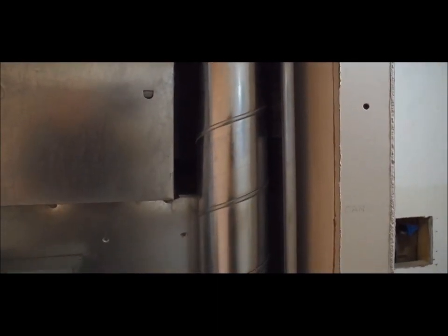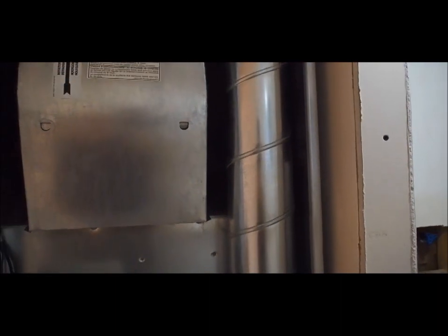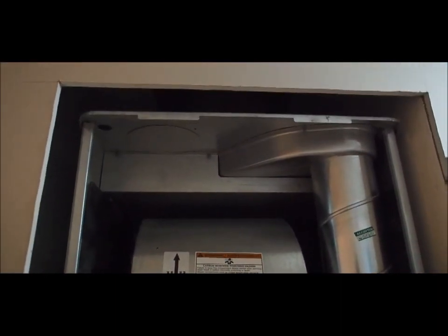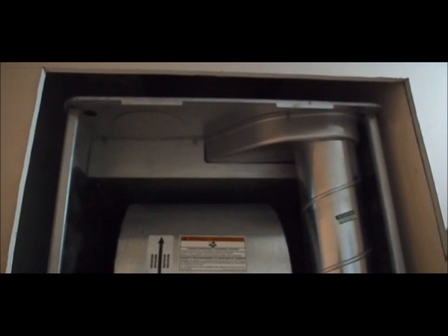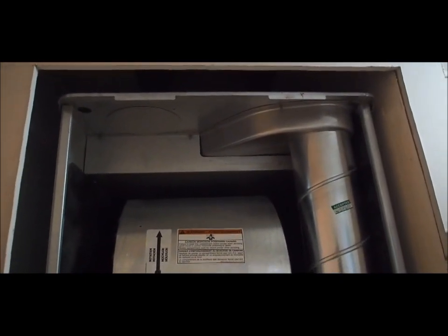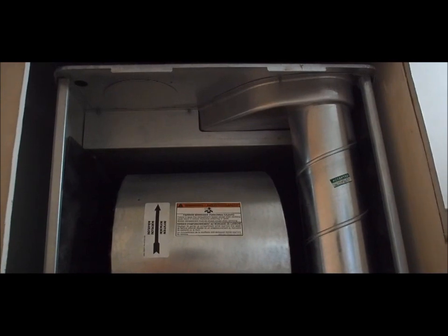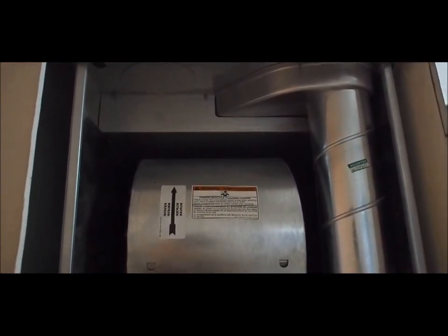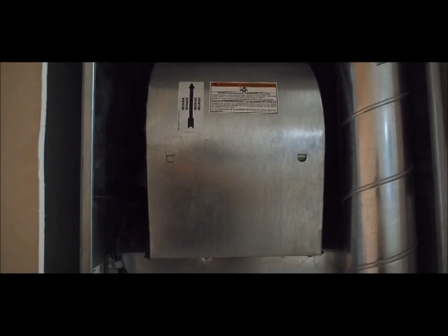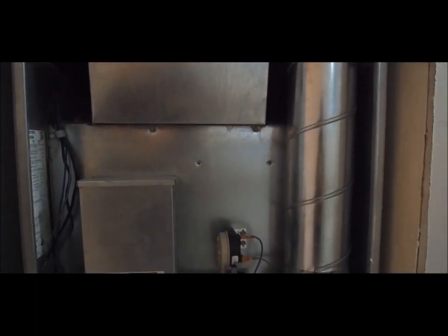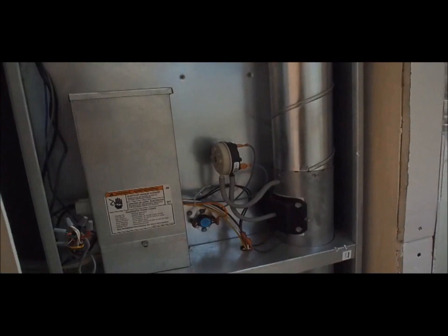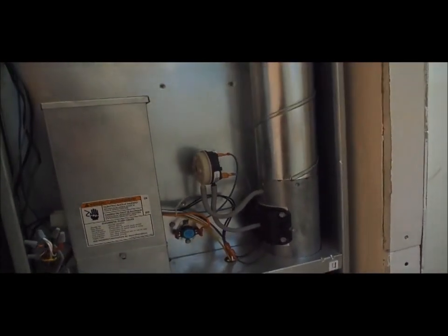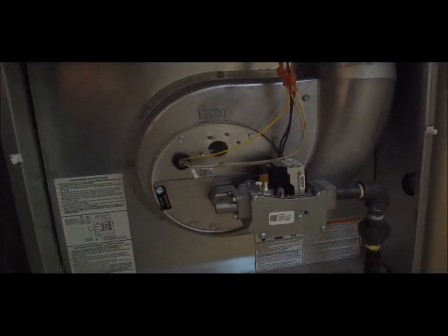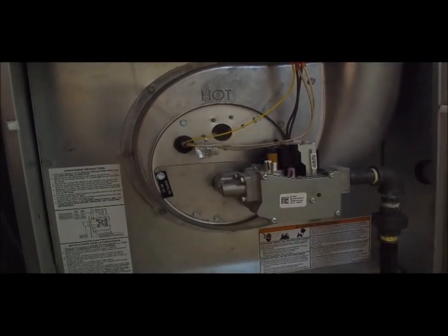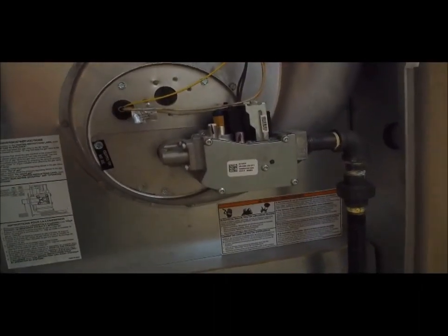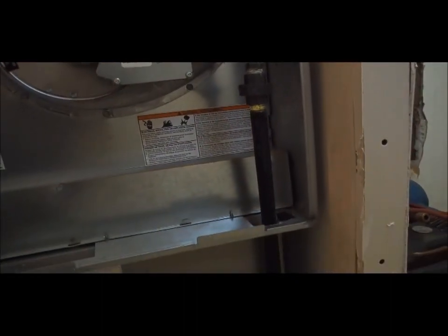So it's a closed combustion system. And the vent for this furnace is called a concentric vent, and so the air for combustion is drawn from the outside, around the outside of the chimney, and then the exhaust gases go up through the middle of the chimney. So I'll take you up on the roof and give you a look at that. But the air basically comes down through that pipe, and then it goes into the firebox, or the heat exchanger, which is in here. This is where the fire is. You can see this is a gas valve. It's connected to that gas line.